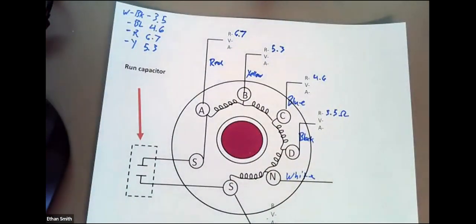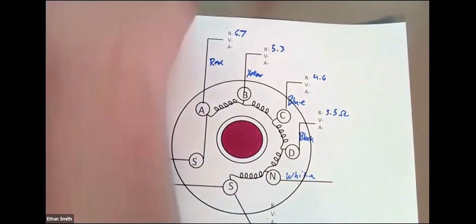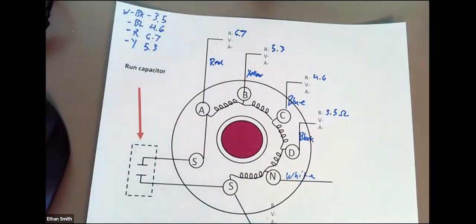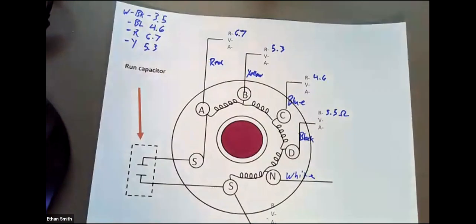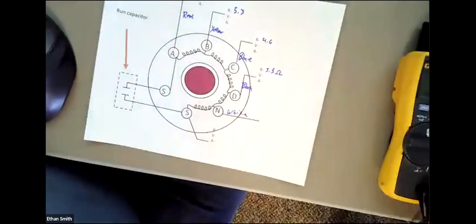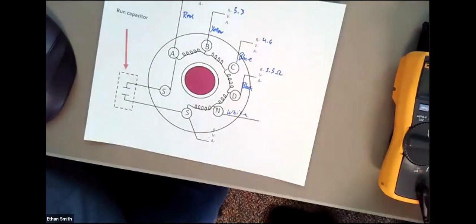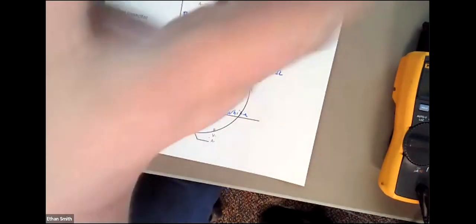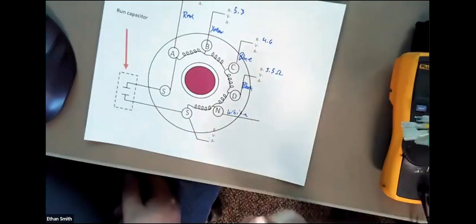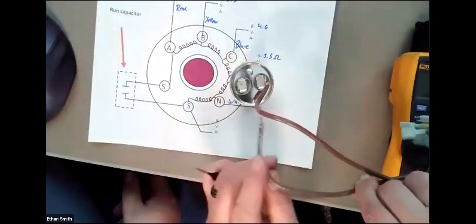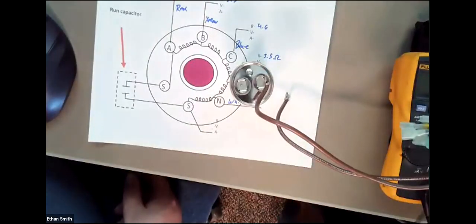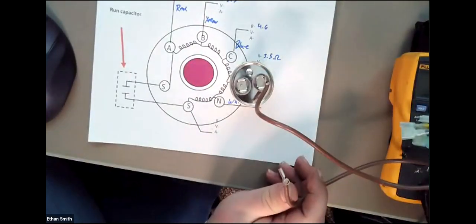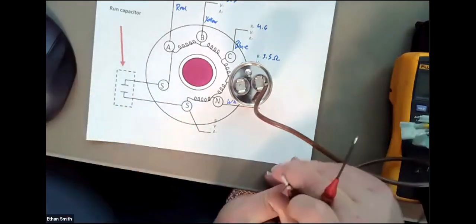Okay. And one thing we didn't do is get our capacitor, because we've got a little bit of winding out here. If we didn't know what that was, we can check it. So let's grab the meter real quick. Grab my lovely assistants back here. We know that's wired up to the capacitor, but just as a check so you know, we've got our capacitor out here. Bring that over here, if you would. You're going to check capacity? Well, we're not going to check capacitance, but we're going to check what the resistance is on this piece of winding here.